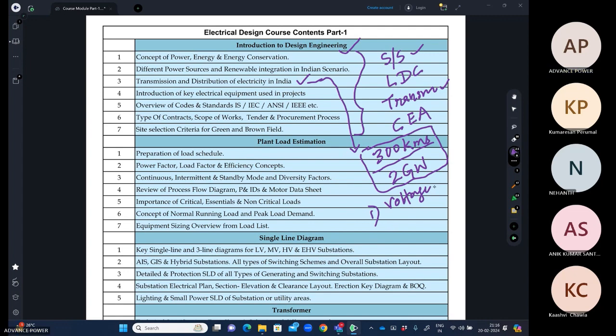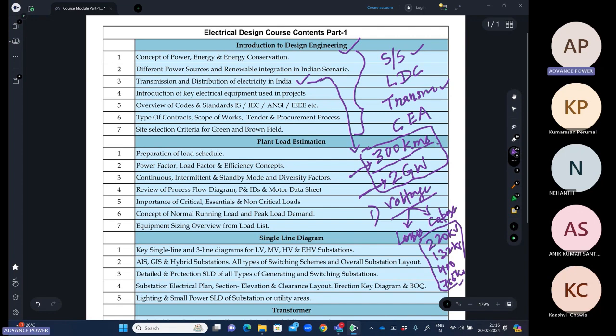isn't it? This will be decided based on the losses in your system and the capex you are spending for different voltage levels. We will develop an Excel sheet during our course in which, by varying the loads, or you can say the generation, and varying the distance of the lines, you will be able to show which voltage level, 220 kV, 132 kV, 400 kV or 765 kV, will be suitable for this type of generation and load.